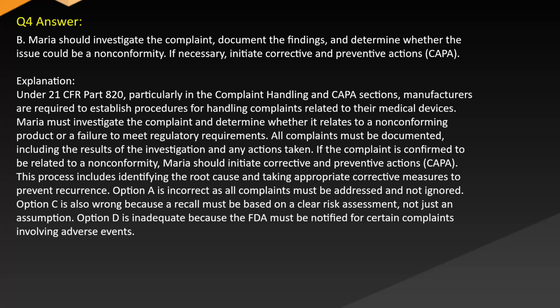Answer. B. Maria should investigate the complaint, document the findings, and determine whether the issue could be a nonconformity. If necessary, initiate corrective and preventive actions (CAPA). Explanation. Under 21 CFR Part 820, particularly in the complaint handling and CAPA sections, manufacturers are required to establish procedures for handling complaints related to their medical devices. Maria must investigate the complaint and determine whether it relates to a non-conforming product or a failure to meet regulatory requirements.